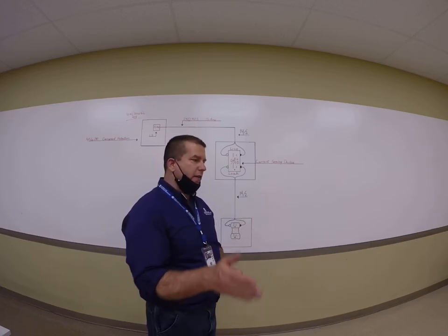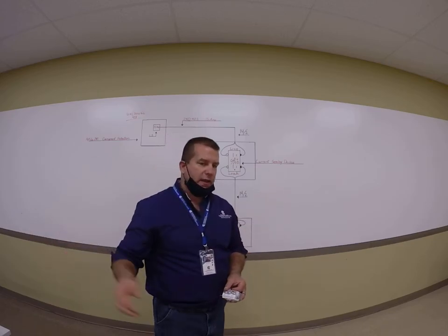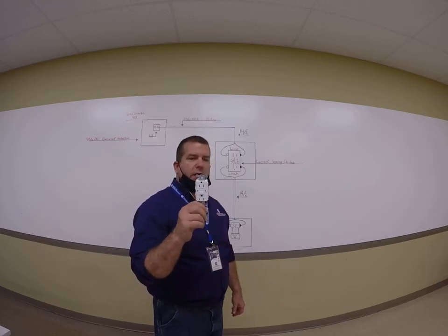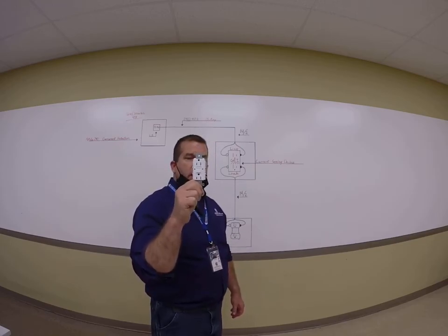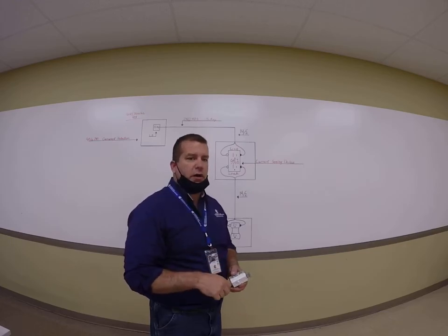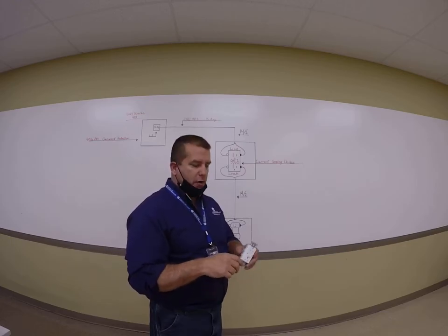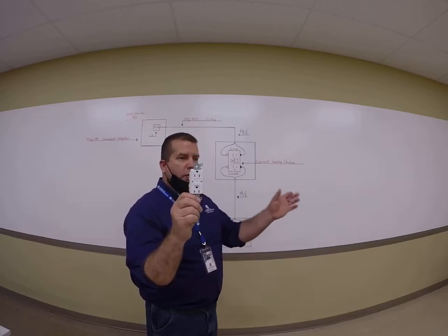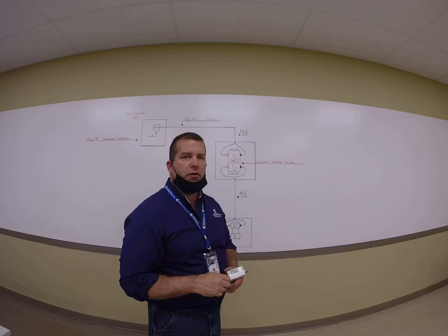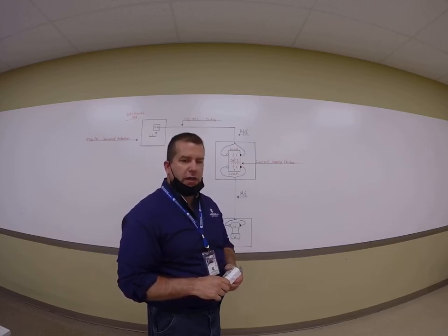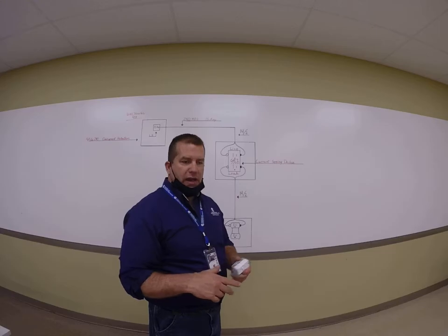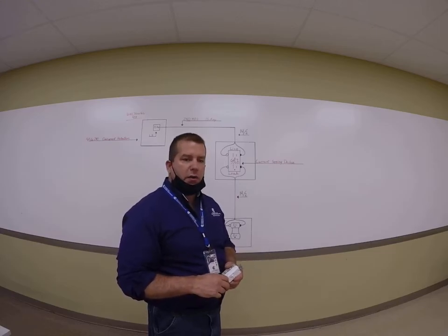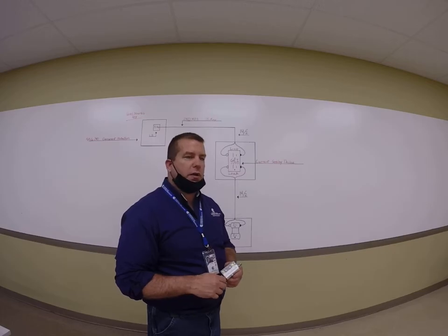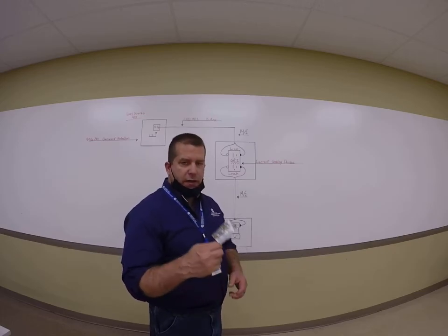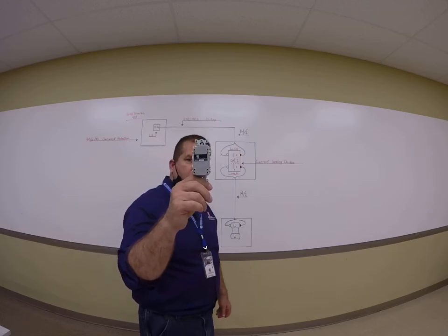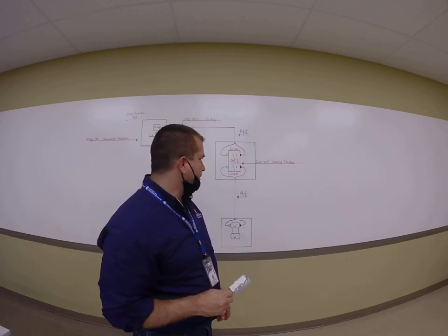So if I wanted to put my two small appliance branch circuits for the countertops, I put one GFCI to the left of the sink, one GFCI to the right of the sink. I have a 20 amp circuit that feeds this one. I have the other 20 amp small appliance branch circuit that feeds the other one, and then I come off the load side of these to regular receptacles elsewhere on the countertops or in other areas of the kitchen, dining, pantry, and similar spaces that also need to be part of that small appliance branch circuit. If I want them to be ground fault circuit protected, they would be on the load side, and really we got to go by the code, so let the code tell us where they go.